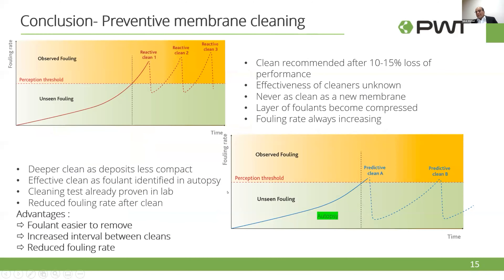Usually there is fouling happening when you start the plant that you cannot see — it's called unseen fouling. When you start to observe it on the graph, the TMP goes up, you clean and it comes down, but the overall trend keeps going up. If you do not control your cleaning regime in this area, you can get this kind of progressively worsening graph.